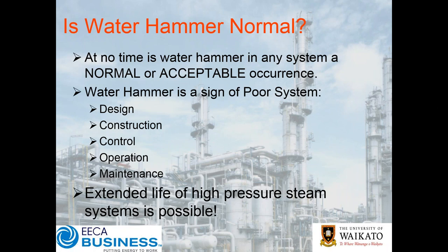I really want to emphasize this point: at no time is water hammer in any steam system a normal or acceptable occurrence. You can apply that same principle to your water reticulation system — the same scenario rules apply. In a steam system, water hammer is not acceptable. So if you're looking at accepting a new build or a remedial upgrade and you have water hammer, you should ensure that's actually a non-conforming performance that needs to be rectified.